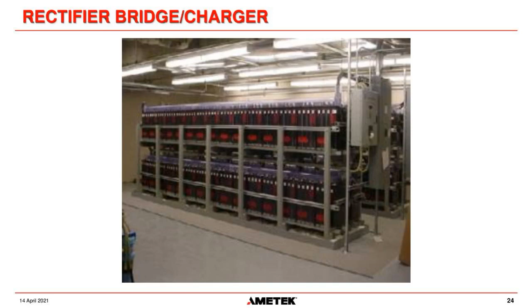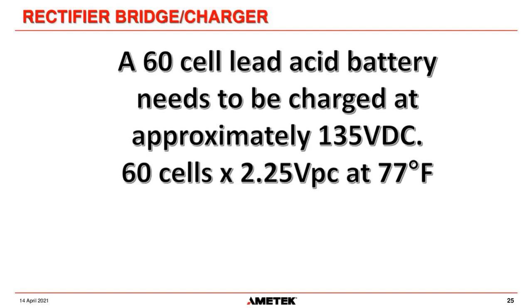So we have to keep these batteries charged correctly. And a 60-cell lead acid battery needs to be charged at approximately 135 volts DC. That's for a 60-cell system, 2.25 volts per cell at 77 degrees Fahrenheit. Always check your battery manufacturer's datasheet to make sure that is the correct voltage for your type of battery, but that is pretty much an industry standard.